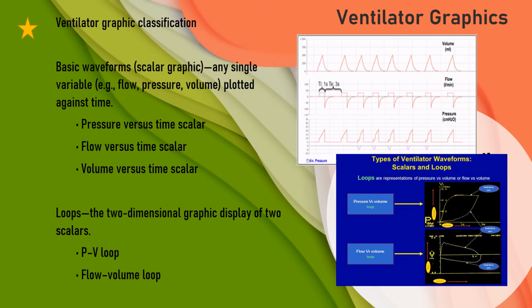The basic waveforms we see on the ventilator screens are graphical representations of what the ventilator delivers to the baby. The first wave shows the volume being delivered at a given time. The second wave depicts the flow of air coming in and out of the baby's lungs. And the third depicts the pressure being delivered to the baby. These basic waveforms, with the variables, are plotted against time.